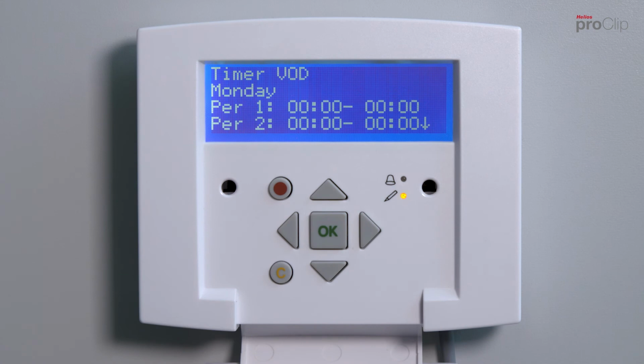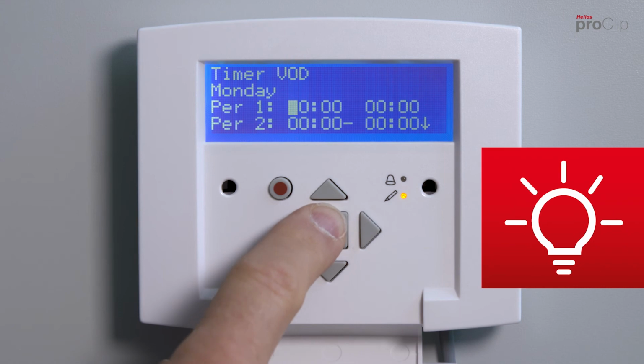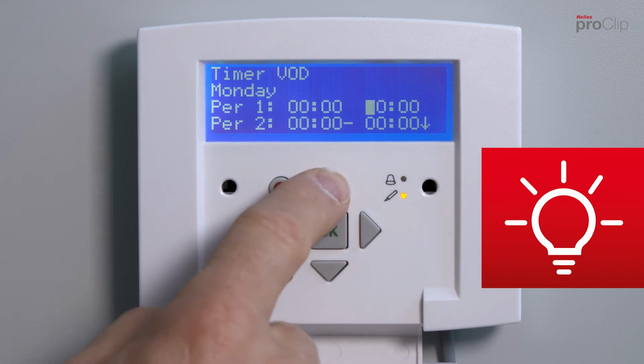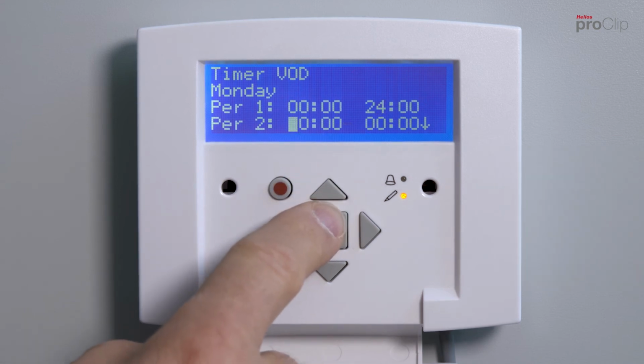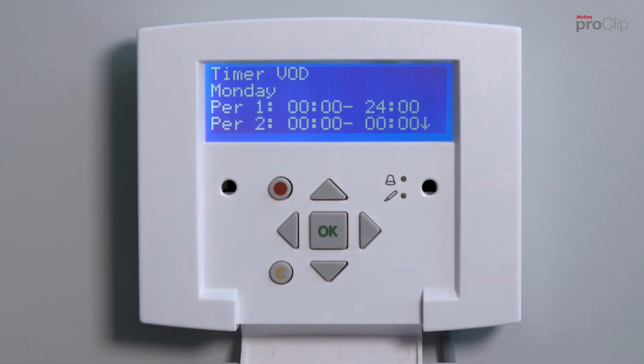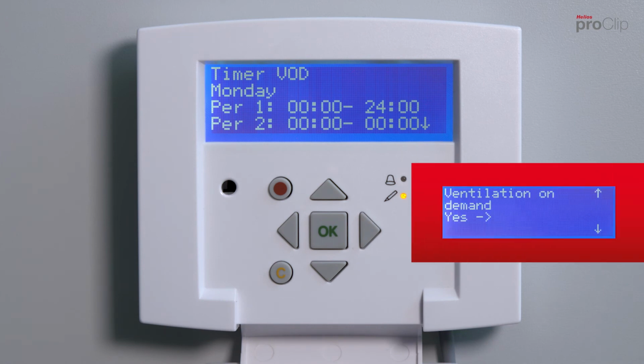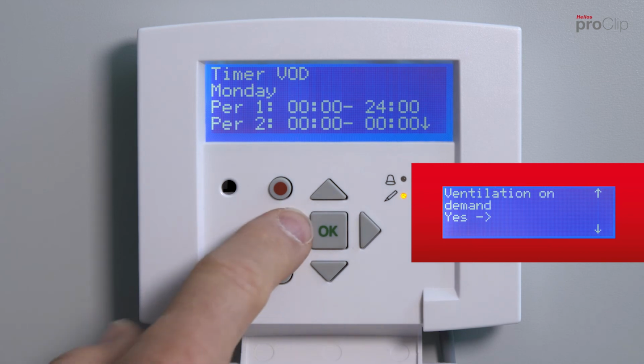Timer VOD. The Timer VOD must be programmed for the automatic operation of the unit using sensors. If there are no specific requirements for system operation, we recommend programming Timer VOD for every day from 0 to 24 hours in period 1. The Timer VOD menu is only available if air quality sensors have been installed and activated during commissioning.